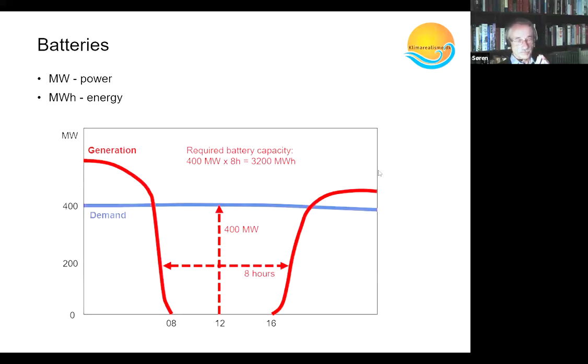How much do we need? Here's how you calculate it. We have a demand fairly steady at 400 megawatts, and generation which starts at maybe 600, 500 megawatts, then drops to 0, then comes back up in the afternoon. The two only match at two points, and in between you need your battery. You can calculate the capacity needed to fill this gap: roughly 8 hours times roughly 400 megawatts gives a minimum battery size of 3,200 megawatt hours. Of course you need a lot more when you take more days into account, but just in this case it's 3,200 megawatt hours, which is quite a lot.